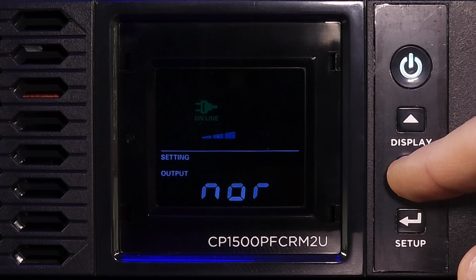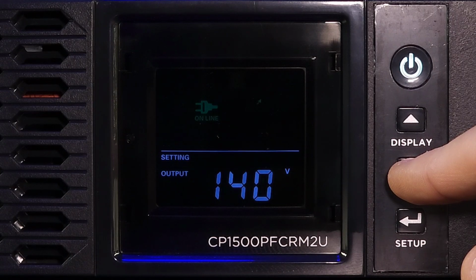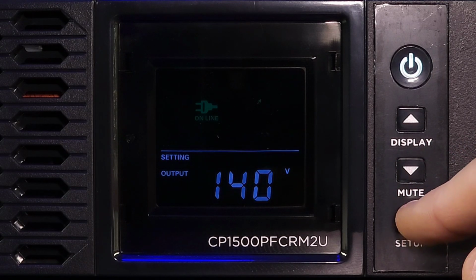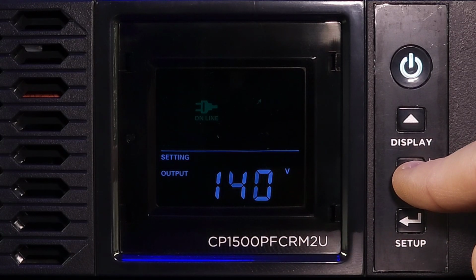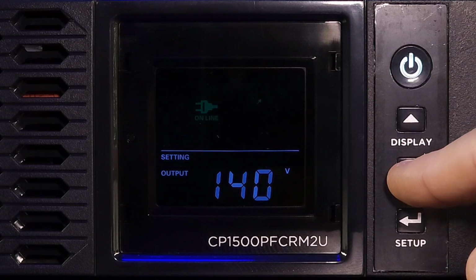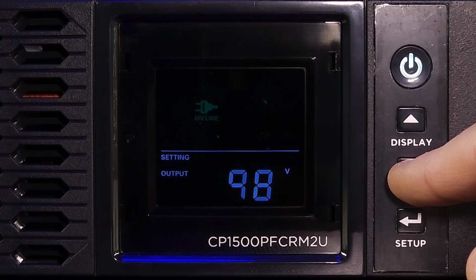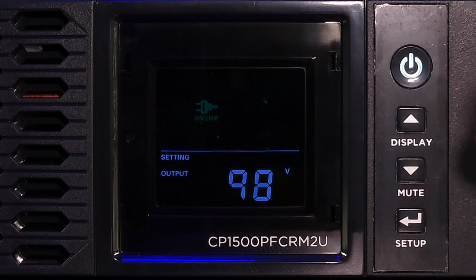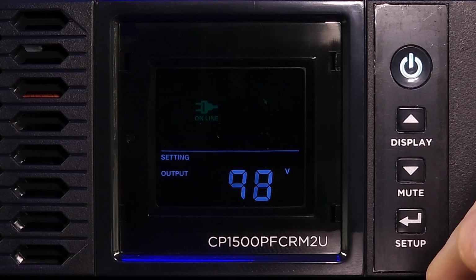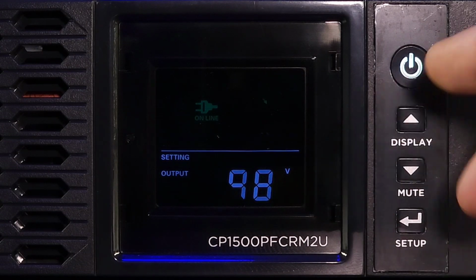Our next option shows a little up arrow, and this is for your utility quality settings - fixed voltage ranges that can be chosen and set. Right now it's set to 140 volts, the default, so I'll keep it there, but you can change that. You can also change your down voltage. It's set to 98 volts by default, but you can change it anywhere from 91 to 103 volts, so you can fine tune the load transfer voltage in this function.